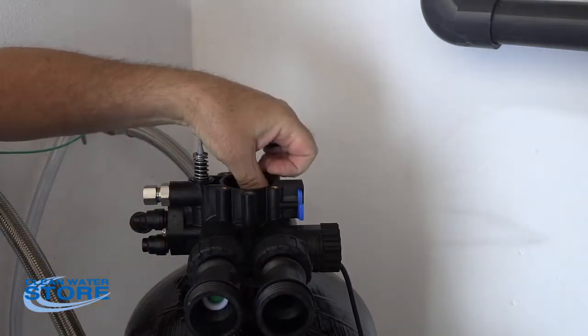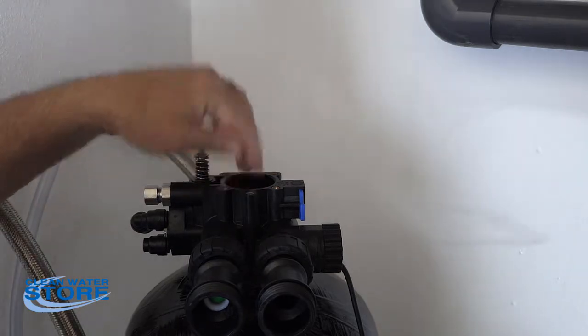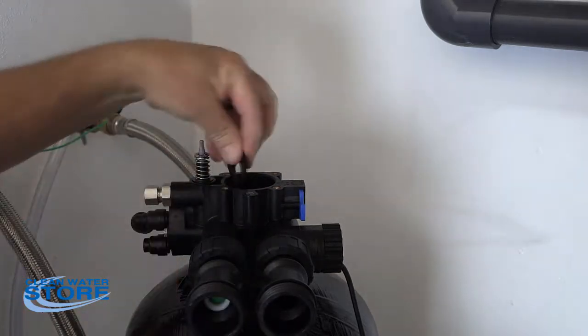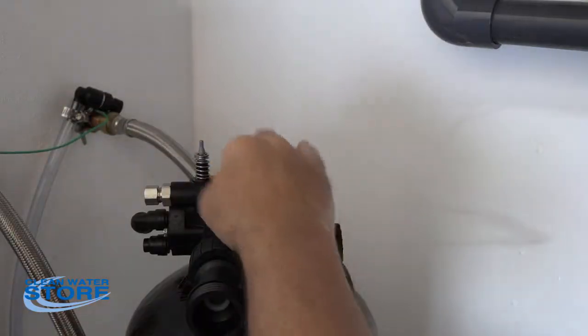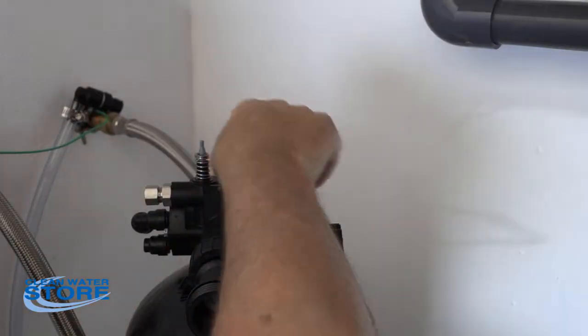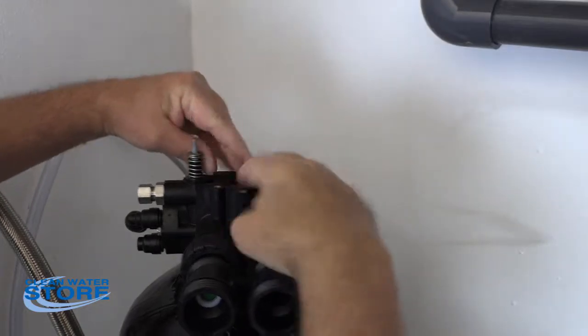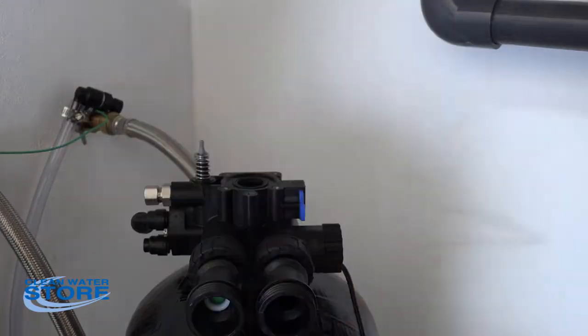Once your bottom seat's in, you want to put in a seal, then the spacer, then a seal. Make sure you lube all these seals up good. Then a seal, spacer, another seal, spacer, and then the last seal. This is going to seal the top of the valve to the body.